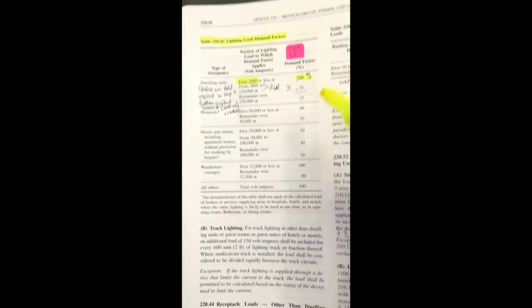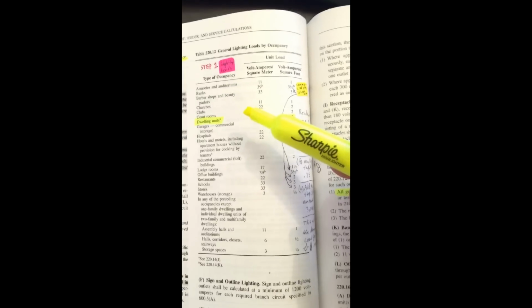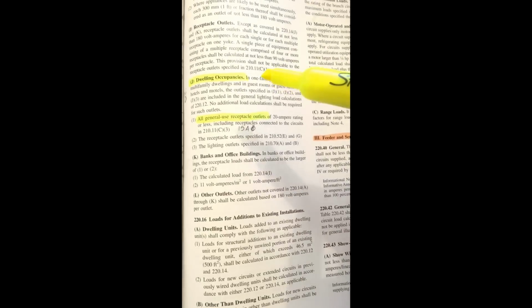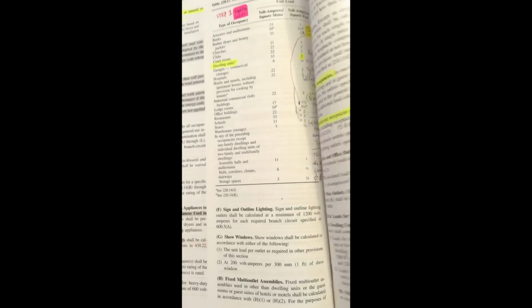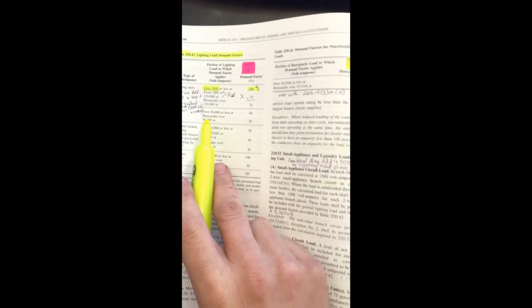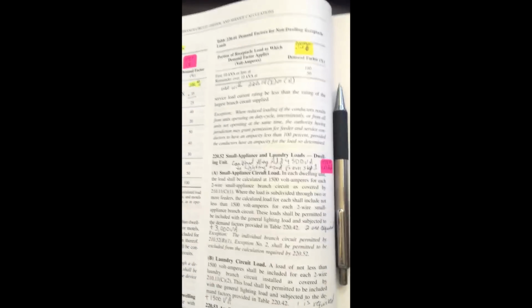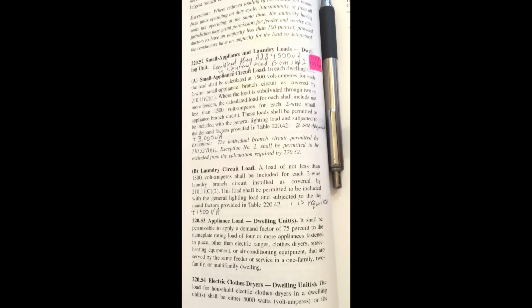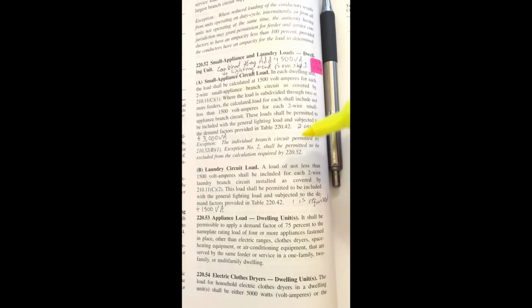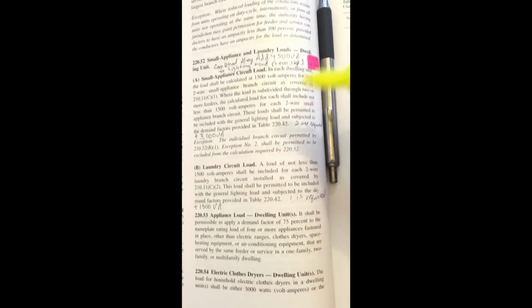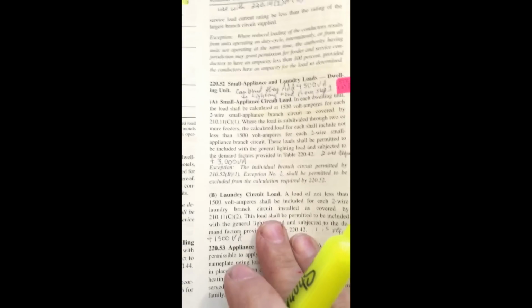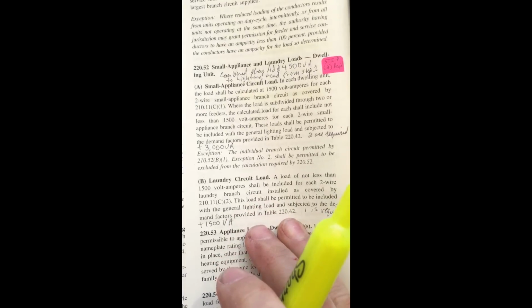Now, before I do this, this number here, back on 220.12, and this little note down here with J being included, J tells me that I'm allowed to include any other required receptacles in my calculated value before I take my derate from this table right here. So we've got one more little section we've got to go to real quick, and that is on the same page as the derating table. This is the 20 amp requirements that are in addition to the 3 volt amps per square foot. And this is special again to just the receptacles in residential dwellings.